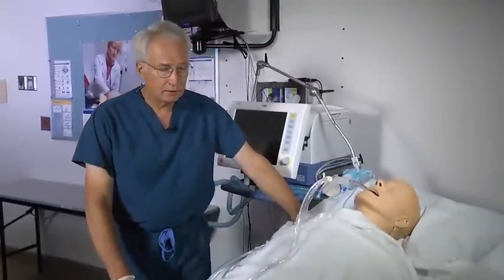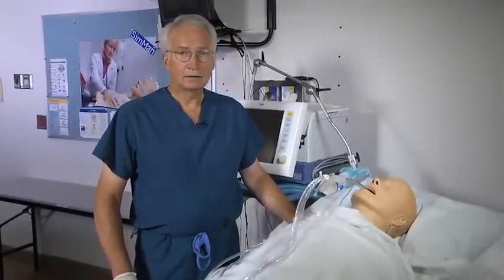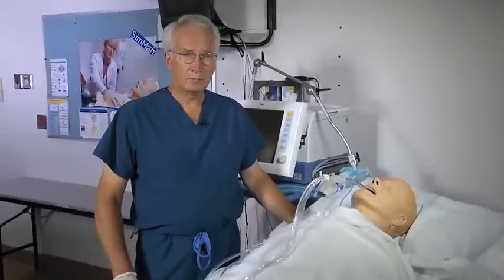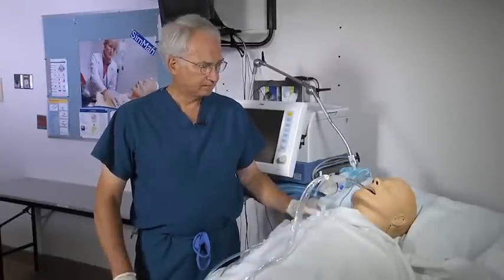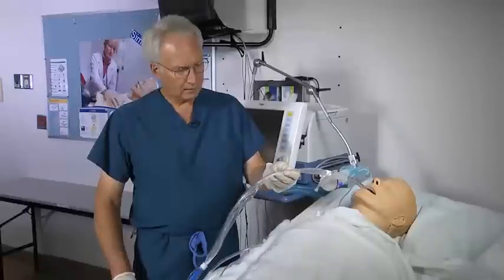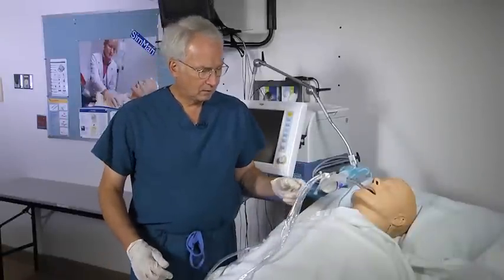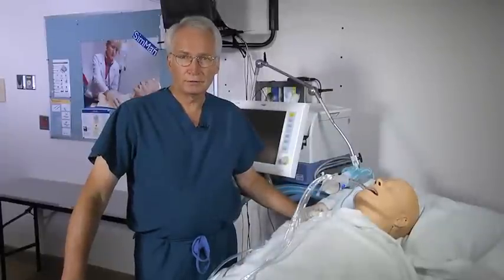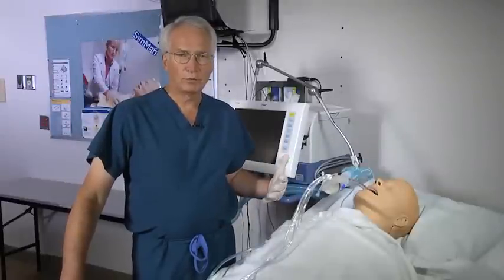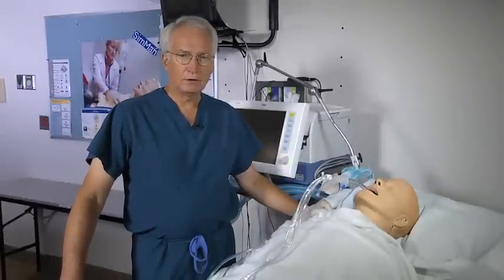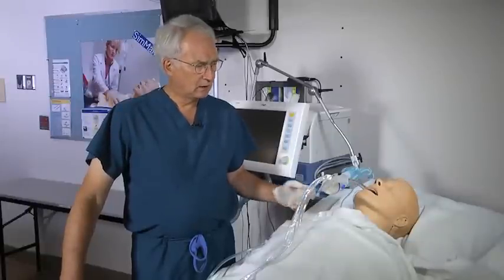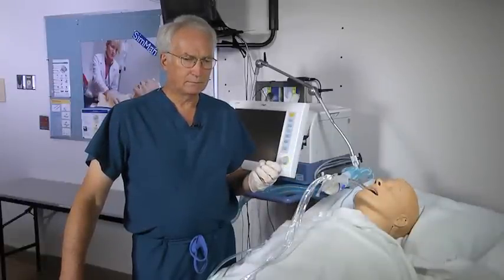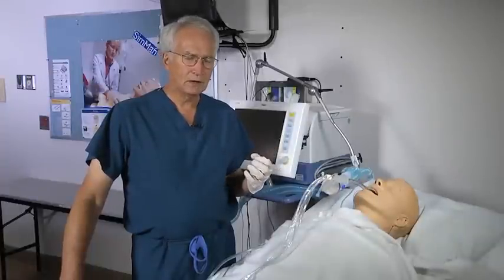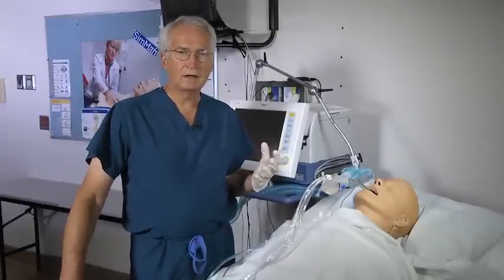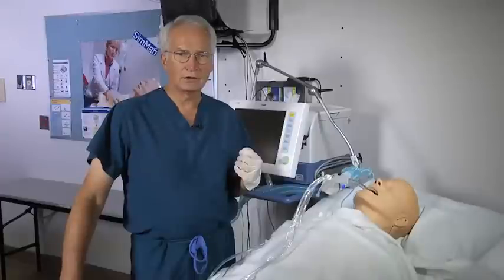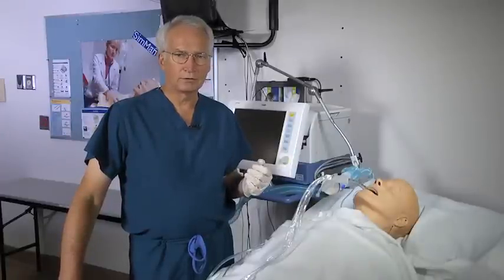Marvin the mannequin has been intubated with a subglottic endotracheal tube that has an inside diameter of 8.5 millimeters. He's attached to the ventilator and a standard closed suction system. What I've done is placed within the endotracheal tube the synthetic secretions, debris, and biofilm-like material that we used in our other demonstration. It's a material that is very viscous, quite similar to mucus and secretions, but if anything is easier to remove by suction than the standard pulmonary and tracheal secretions.